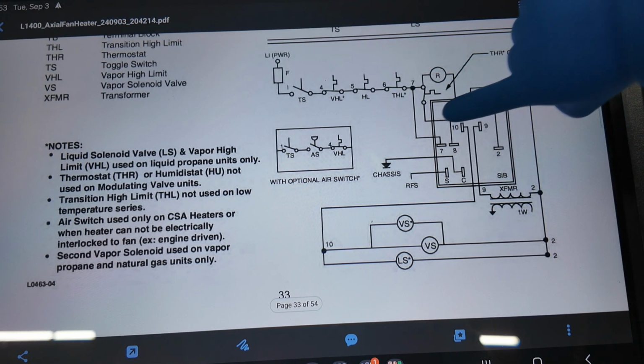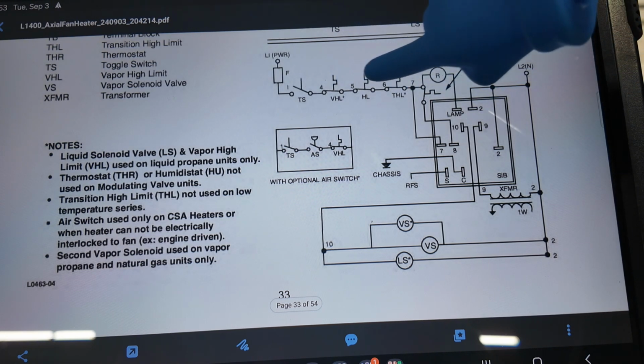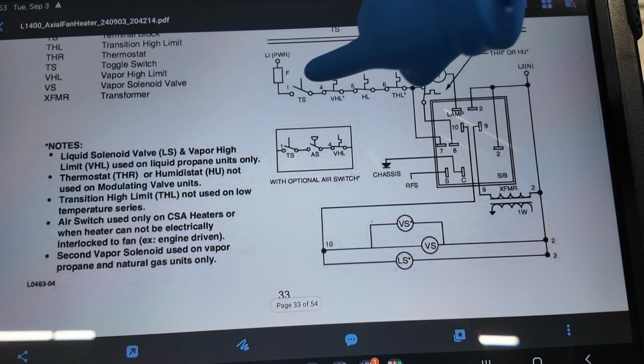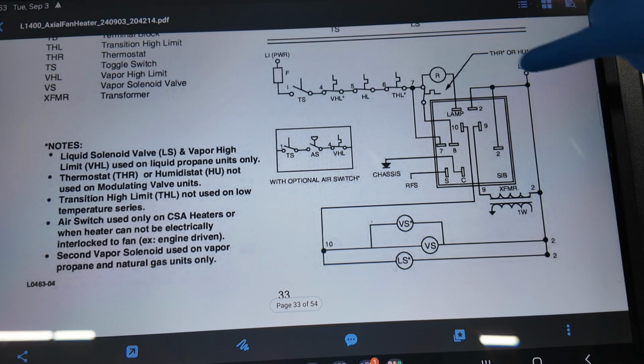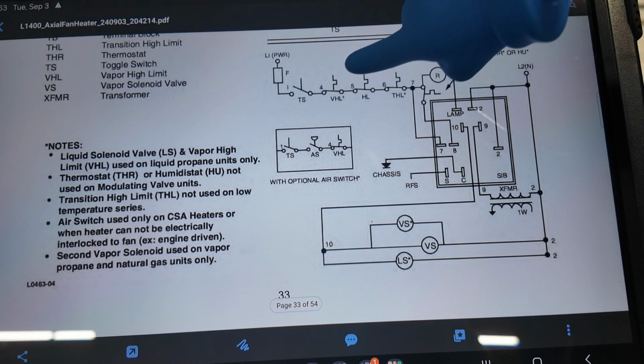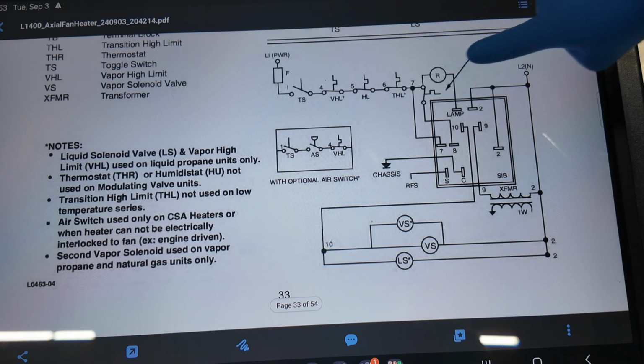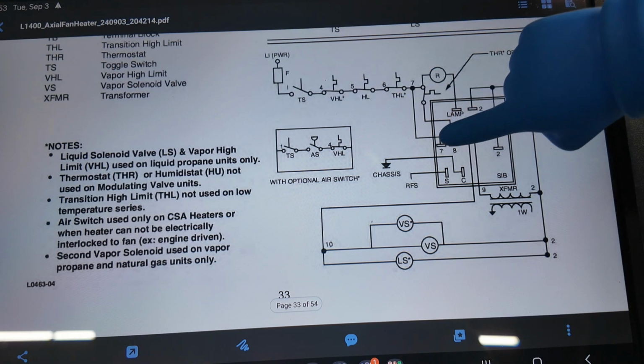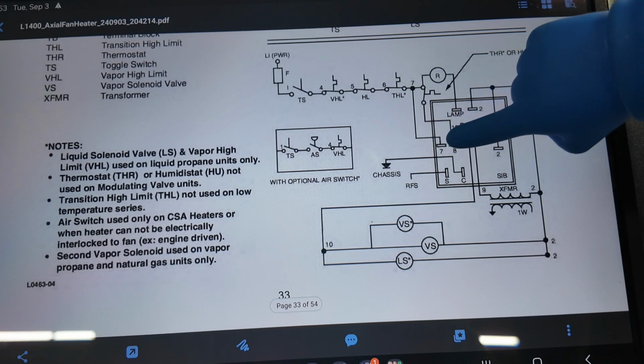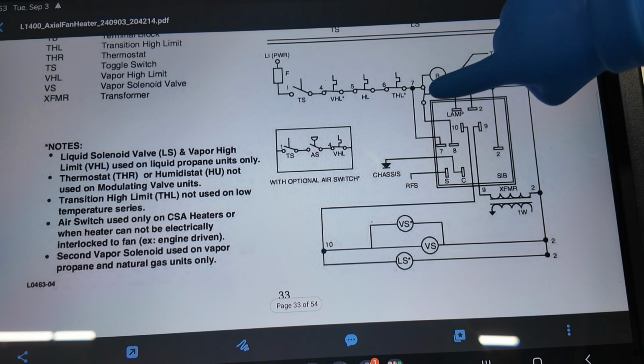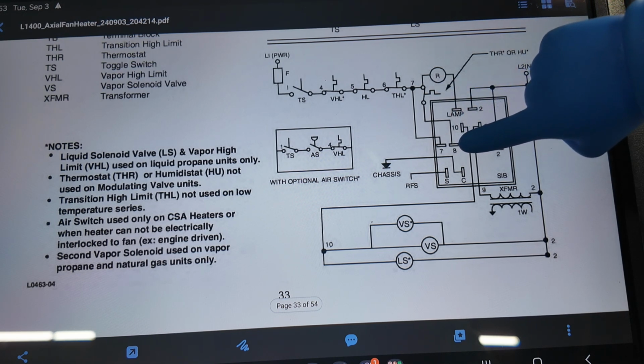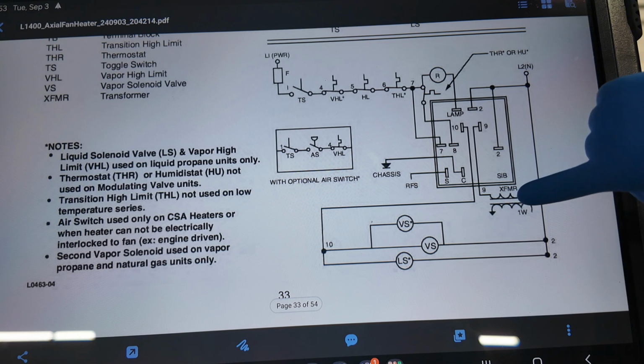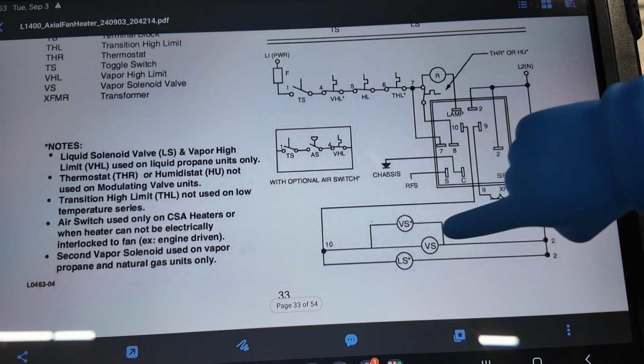So on here, this is how you would troubleshoot. You'd check from your L2 to your power, after your fuse, terminal 4, terminal 5, 6, 7, right through, troubleshoot, make sure you have power on 7 and 8. When you power 7, it starts your purge time. Your purge time goes for about 15 to 20 seconds. And then if you have 110 voltage on terminal 8, you will get spark and you will get gas.